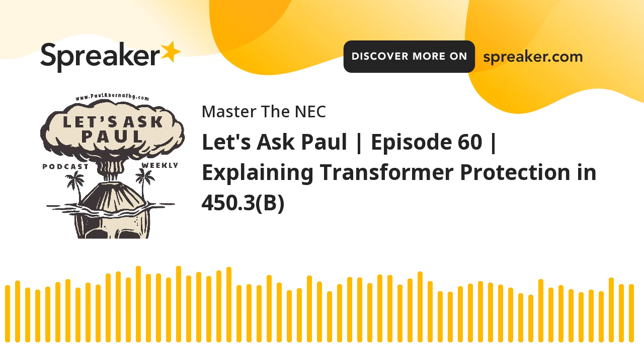So, that being said, this table is nothing but protection for transformers. Now, looking at the notes, I kind of explained what Note 3 was. You have Note 1. Note 1 is the one that tells you, hey, if it's 125% of the currents and you're using this, knowing that you could do all this at 100%. Now, people lose sight of that. This is a maximum. If I don't want to do any of these percentages, I could do the primary protection at 100% or whatever the rated current is of the transformer, and the same as secondary. I could do that if I want. But you have certain inrushes and things like that, so they allow you to go up to a certain percentage and still consider the transformer protected. That's fine.